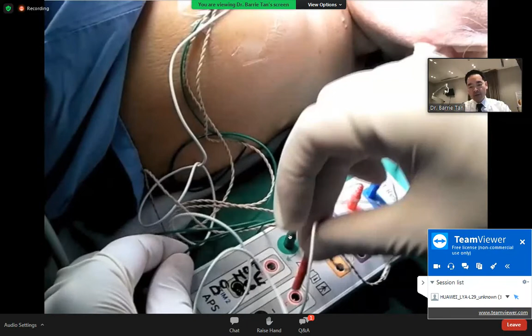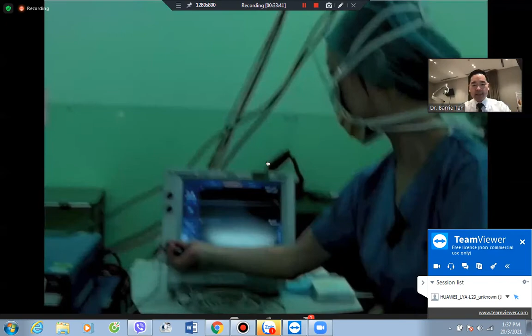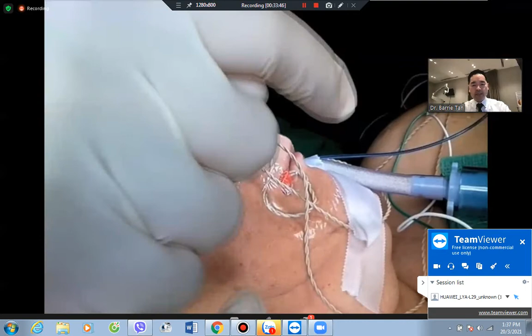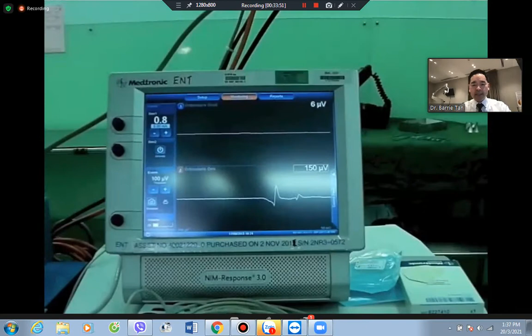And after you've inserted that, you need to plug it in. So plug it into the facial nerve console with the ground electrode to the green, the stimulating electrode into the stimulator. Switch on the machine, set up your otology setup, identify the orbicularis oculi as well as oris, and note that you get waveforms and the sound when you tap on the electrodes themselves to indicate that there is movement of those muscles that will be detected by these EMG electrodes of the facial nerve monitor.